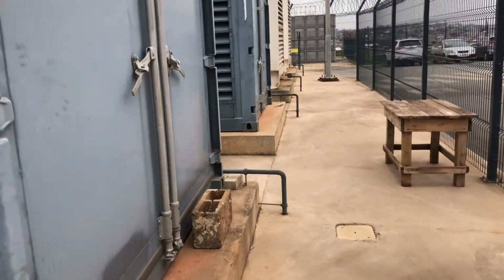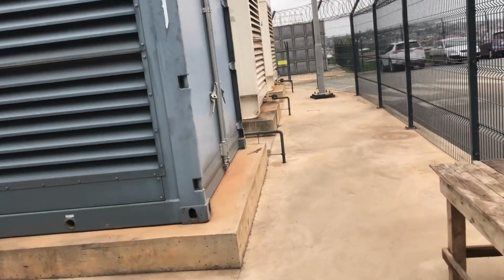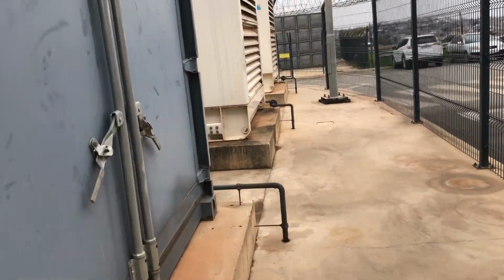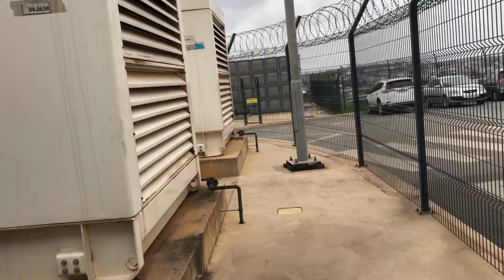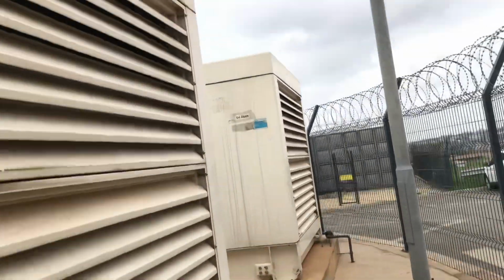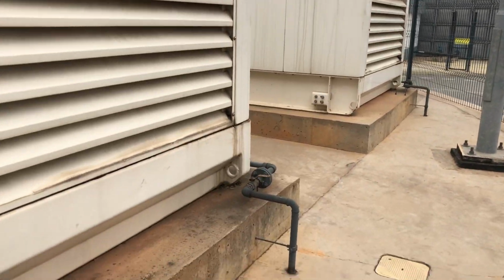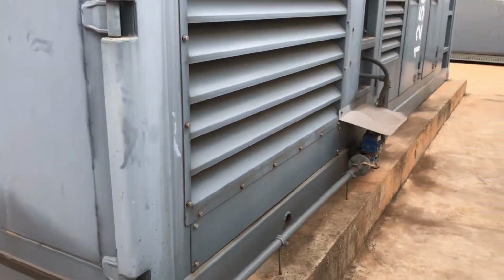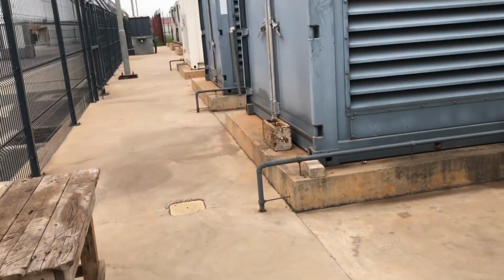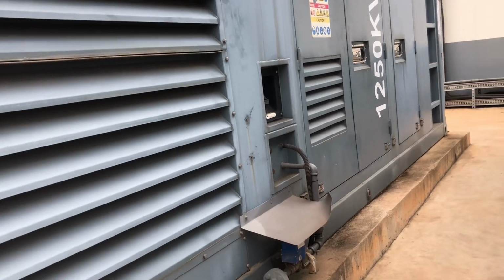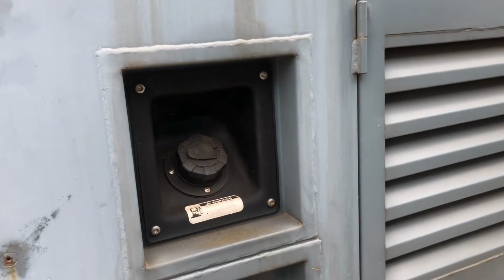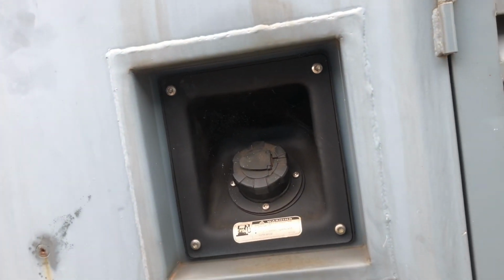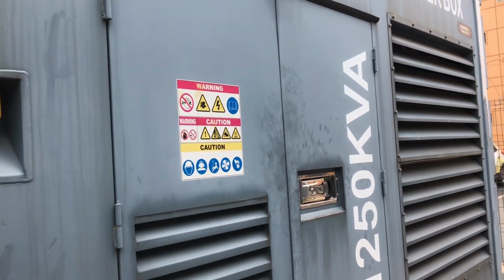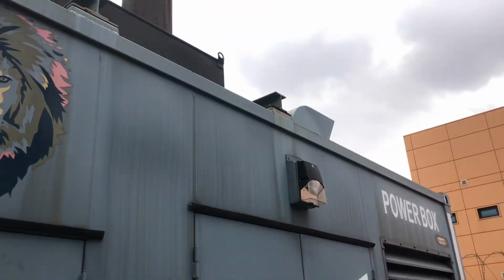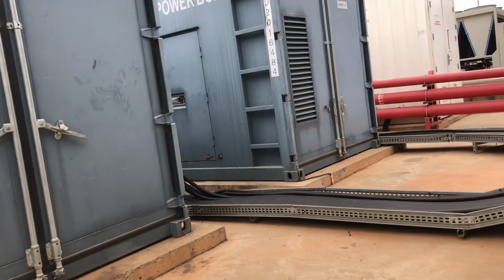So the pipe, you see the pipe here, these pipes are connected to the bulk tank. For that bulk tank, we also have a pump that is attached to the bulk pump. So in a situation where we have to refuel the genset, we just have to switch on the pump. Those pumps are mostly automated, and this particular one that I'm talking about is also automated, so you need not be worried when it comes to refueling the genset when there is a fuel shortage.